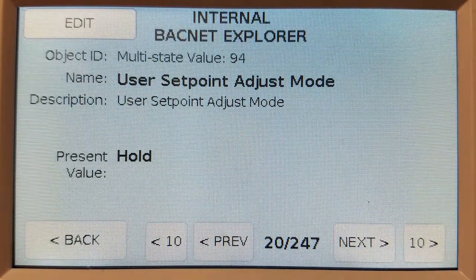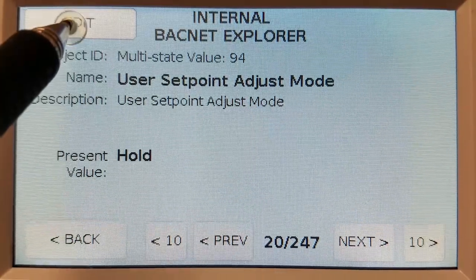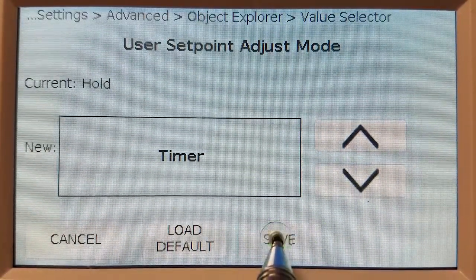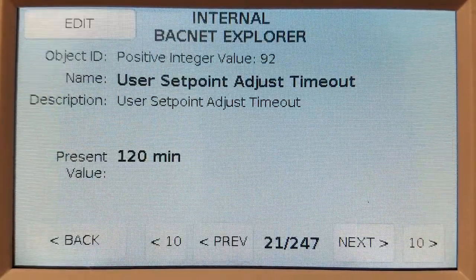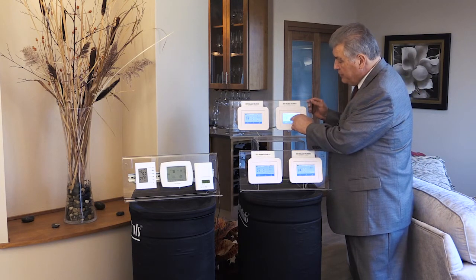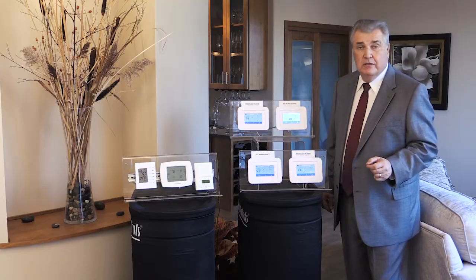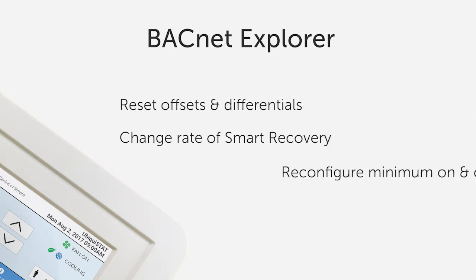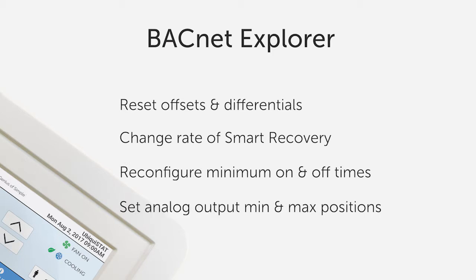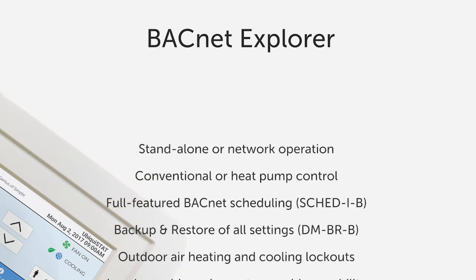If you want that user setpoint adjustment to return to the program setpoints after a couple of hours, simply change the mode to timer and set the timeout to 120 minutes. Now, if the user lowered the cooling setpoint from 74 to 72, it will automatically return to 74 after two hours. And there are dozens more functions available on the built-in Explorer: reset the offsets and differentials, change the rate of smart recovery, reconfigure minimum on and off times, set analog output minimum and maximum positions — the list goes on and on.